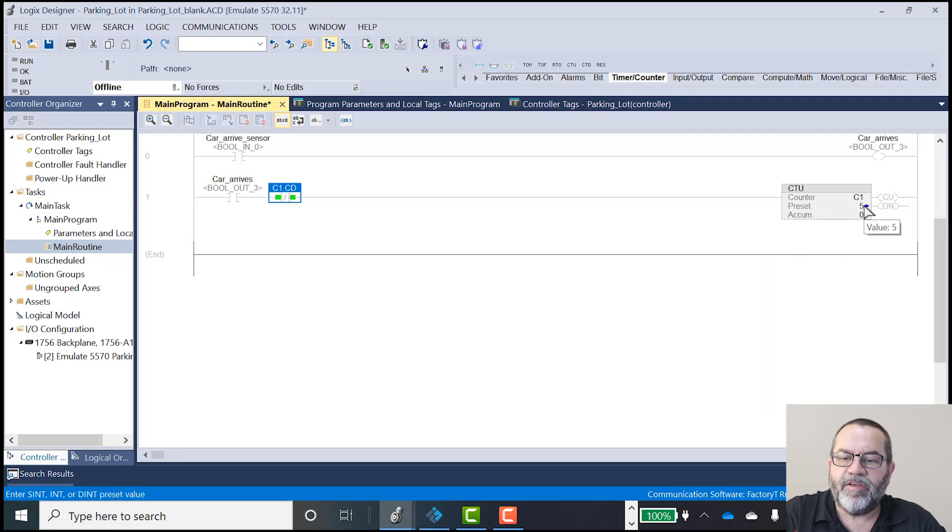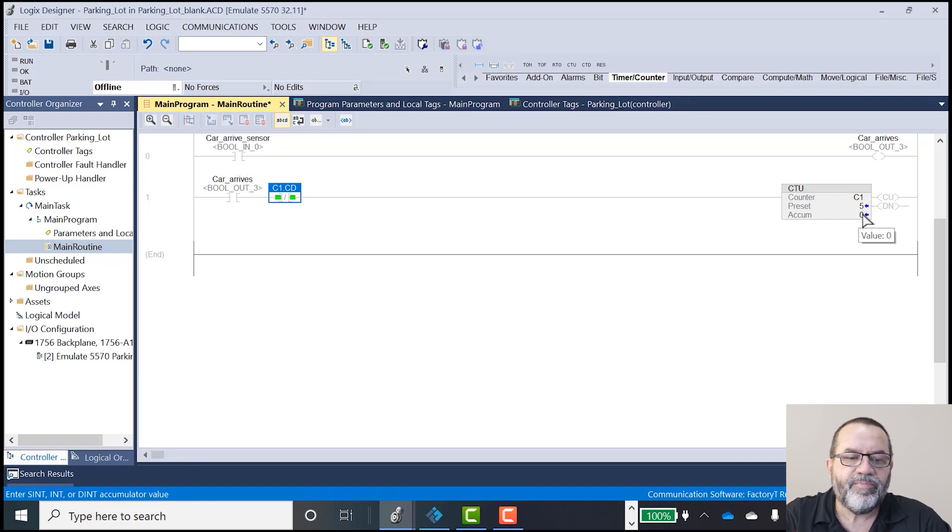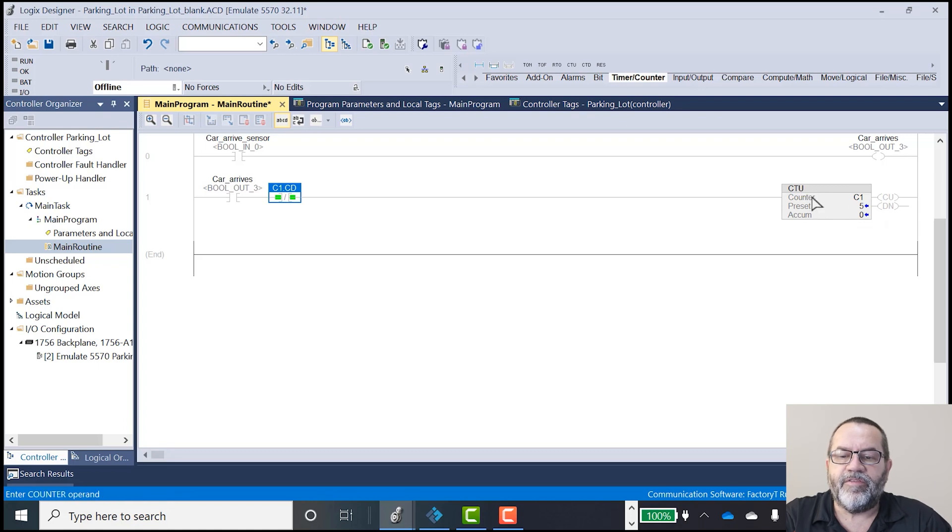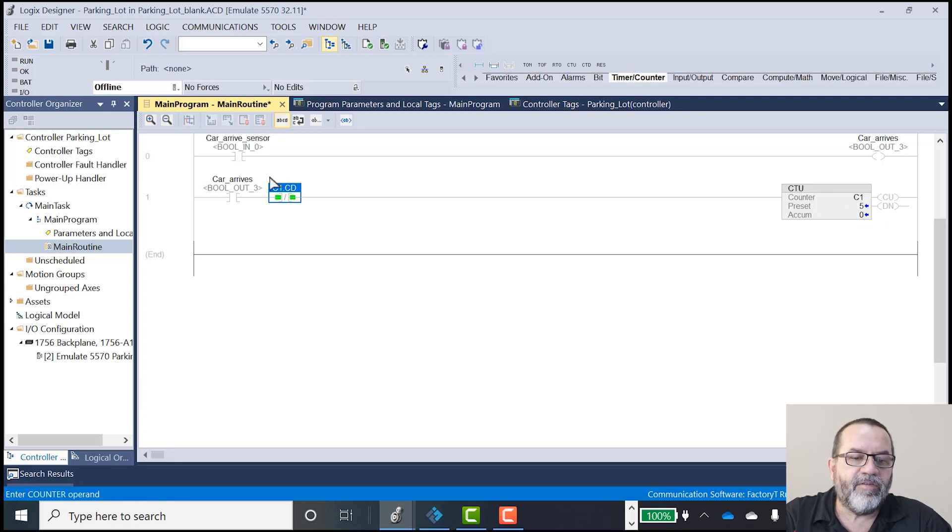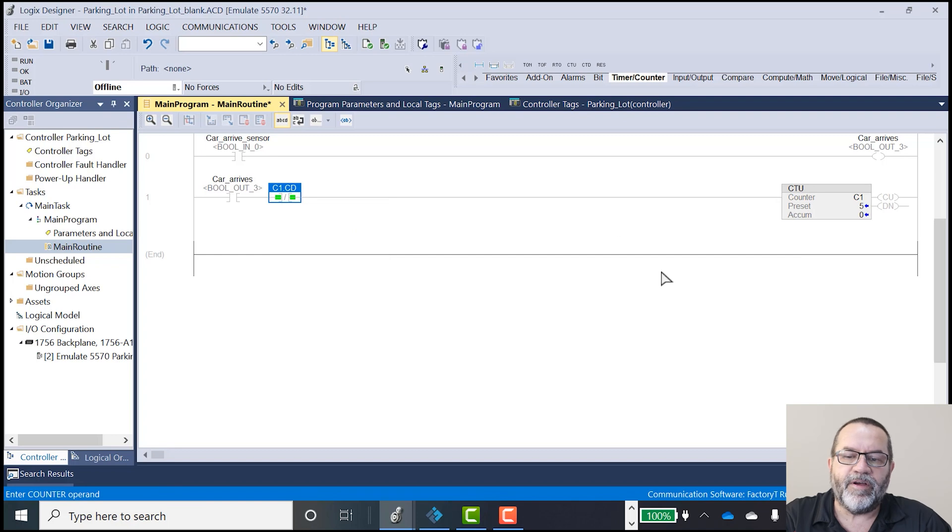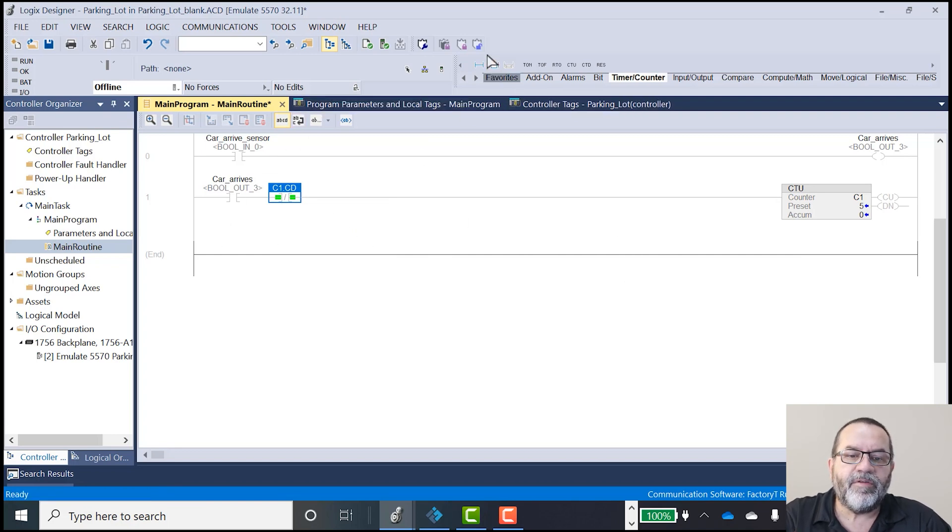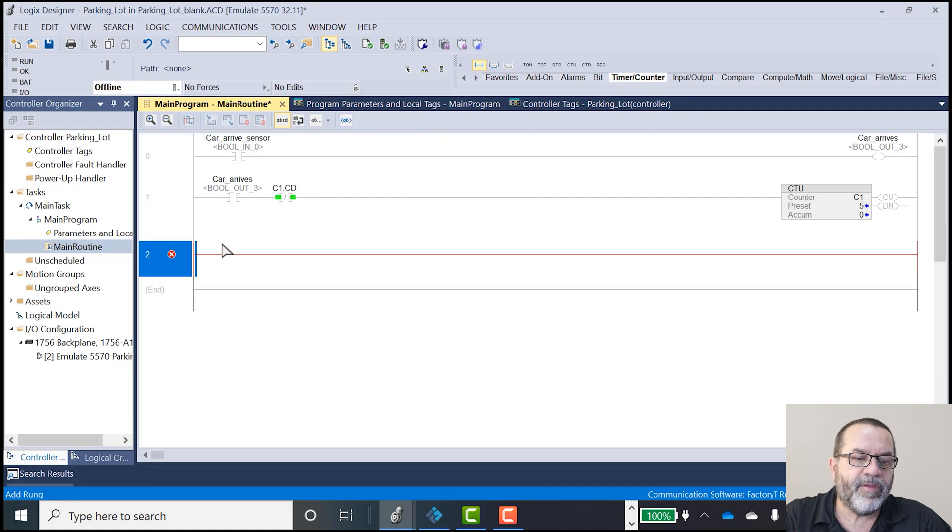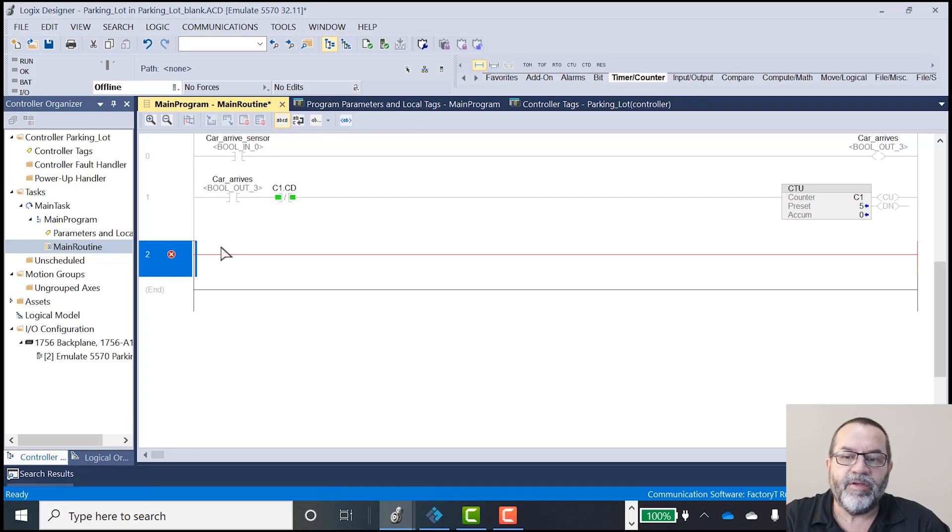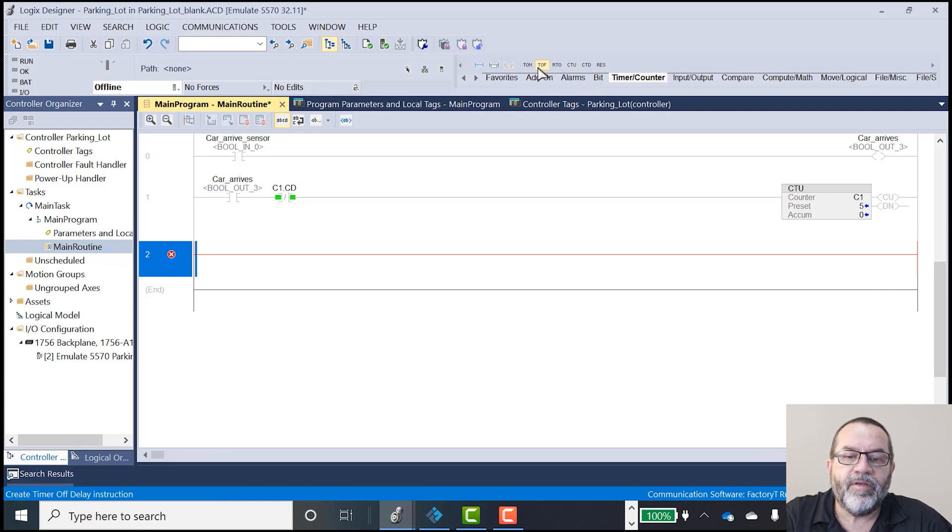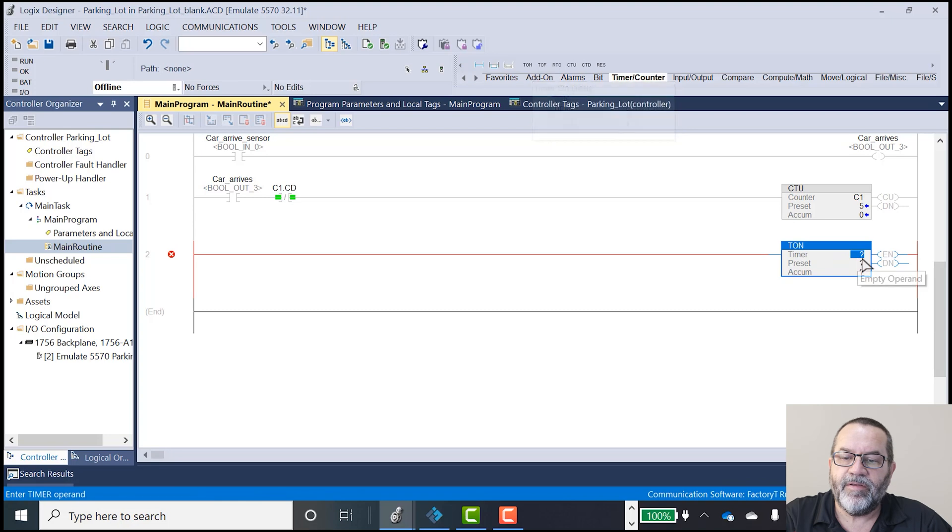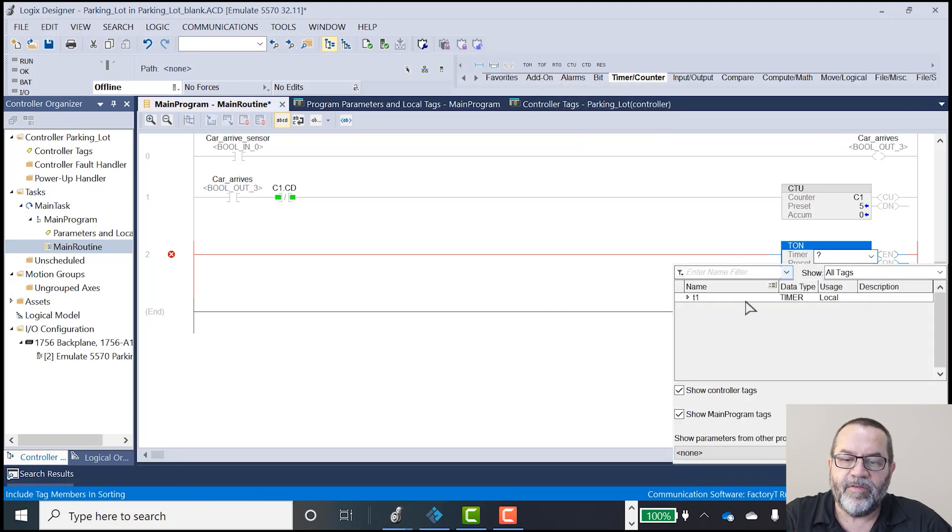And my preset, I've already got it at five. And this will show how many it's accumulated. So if C1 counter is done, then this done bit will block it from going up. Okay, there's my counter. I'll put in another rung. And I want to start my timer here. So I'm going to put a timer on. So that timer is T1. It's the only one I have.